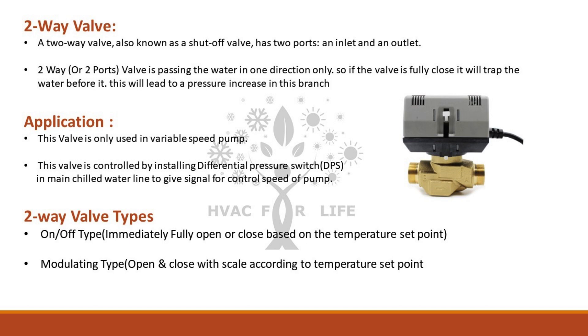Application: this valve is only used with a variable speed pump. It is controlled by installing a differential pressure switch (DPS) in the main chilled water line to give a signal for controlling the speed of the pump. Two-way valve types include the on-off type, which immediately fully opens or closes based on the temperature set point, and the modulating type, which opens and closes in scale according to the temperature set point.